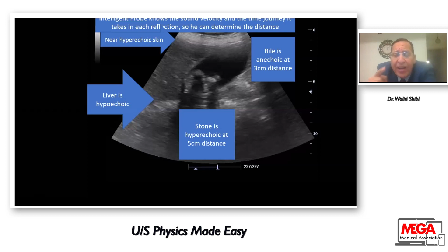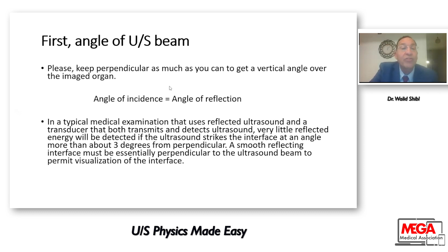Number one, according to the density will appear the echogenicity, and according to the delay of the reflected wave will appear the depth of the organ or the structure. These two rules are very important in governing the ultrasound image you see on the screen. So how can you use this physics in daily practice? Number one, please try for good reflection. Because of that, try to be vertical as much as you can in the organ you need to explore. Try to get a 90-degree angle to get a very good reflection. Because good angle, good reflection. Bad angle, very bad reflection.